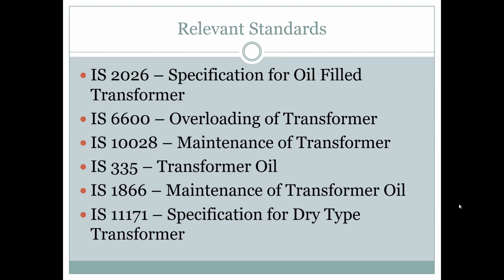Then IS 11171, that is the specification for dry type transformers: how to use, how to design, what precautions to be taken for dry type transformers. Now, transformer oil has a breakdown voltage. We test for it. Whatever is required for the transformer, when we buy new oil, it is less. We demand 60 kV peak, that at 60 kV peak it will rupture, it will not lose its insulation.